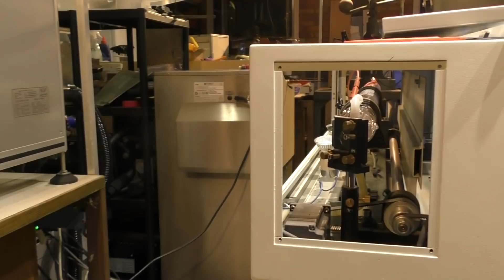Now, when I remove my target from mirror number 2, you may see, I don't know whether there is any haze on there, is there? I will just give it a quick touch to make sure. We don't need to look at mirror number 2 because we've just set the beam to the centre of mirror number 2. And just because we twist the mirror very slightly doesn't mean we're going to upset the centre of the beam on mirror 2. What we're going to do is steer the beam off of mirror 2 onto mirror number 3, which is this mirror here.